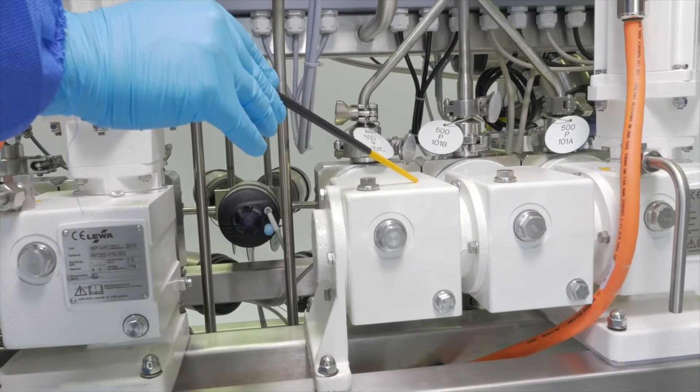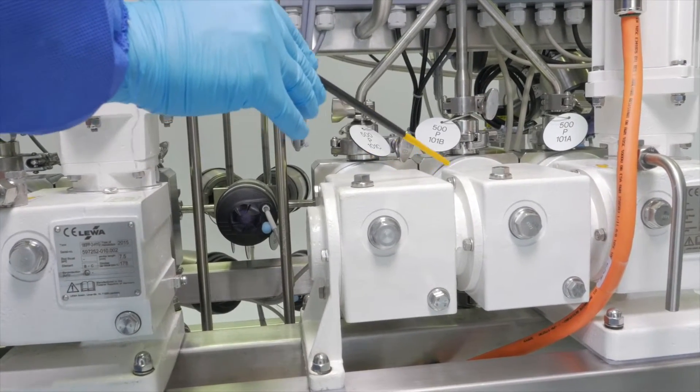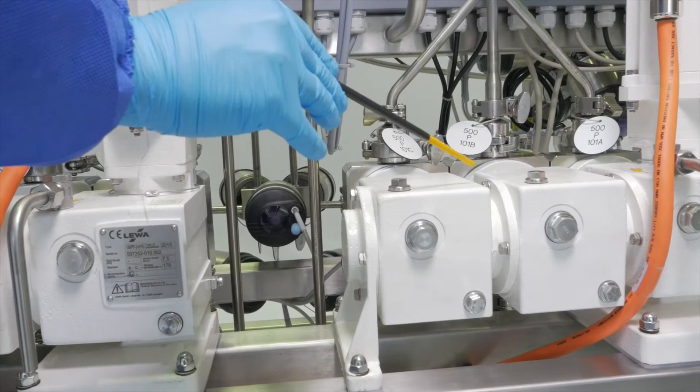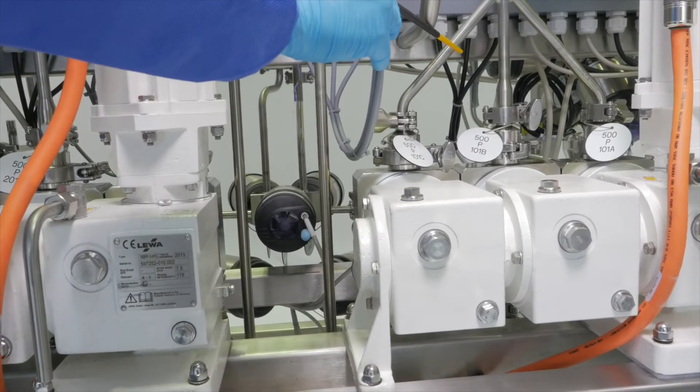A third pump option provides the user the ability to create buffers from concentrate, combining chromatography and buffer dilution in a single skid. The user can select up to four inlets for this pump.